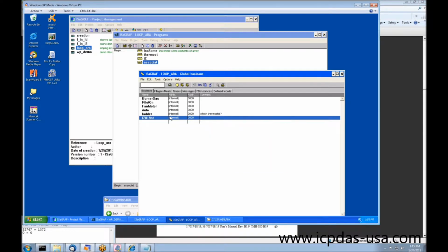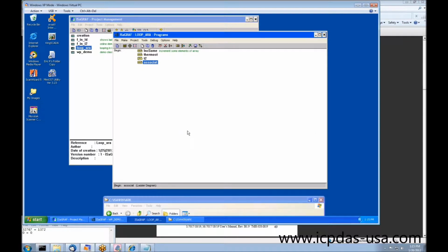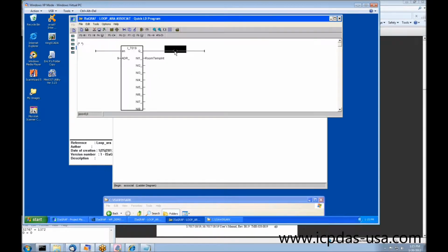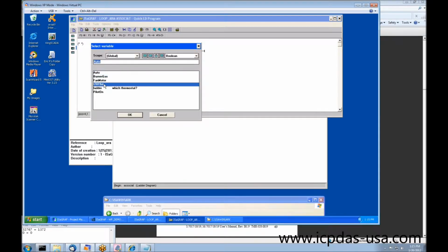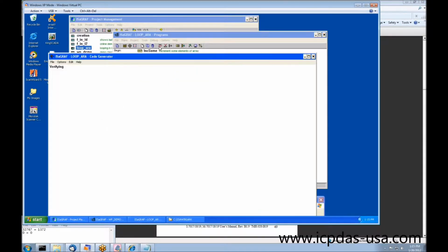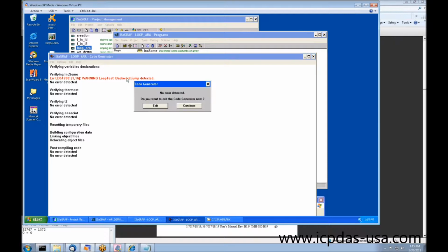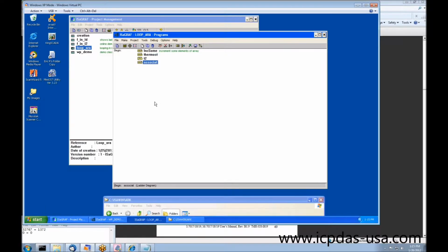I-7019 status. Again, it's an internal because it's a remote module. In this case, it's not even on the function block of the remote module. It's on the output. And there it is. Okay, so let's check again. Let's see if we have communication with that module. Always our warning about the loop.